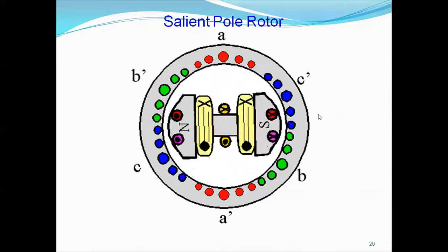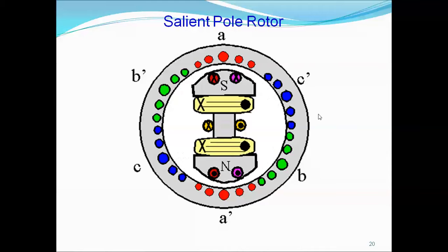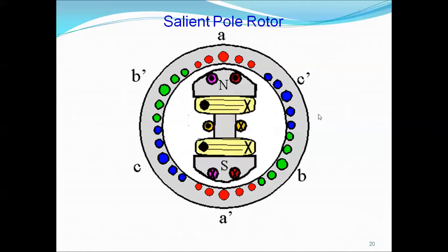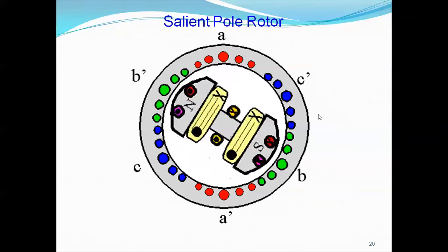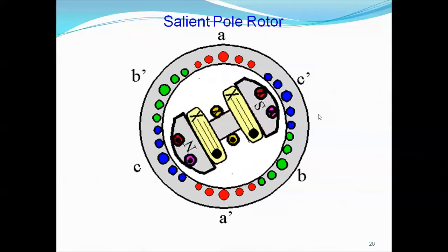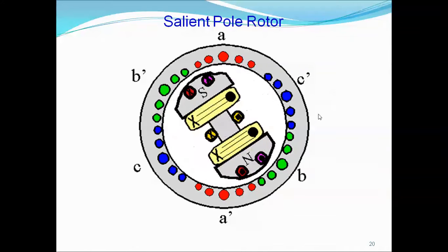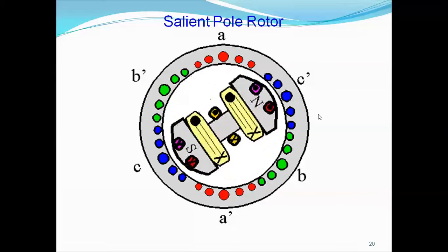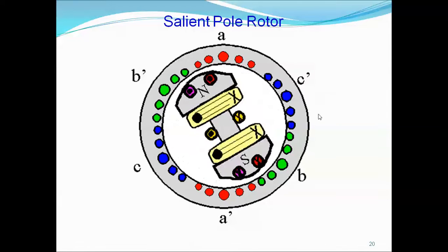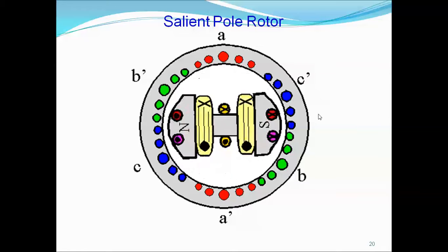As I told, a disadvantage of the synchronous motor is that hunting is produced, so to reduce that we use the damper winding, and it produces high starting torque. The field coils are placed as shown in the figure, and all are connected in series. The ends of the field windings are connected to a DC source through slip rings.